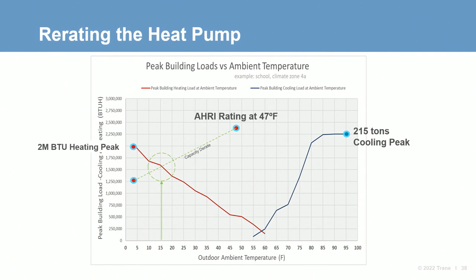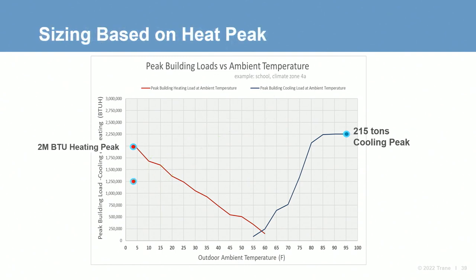To properly size heat pumps for this plant, we need to use the heating peak as our starting point. For our example, sizing based on heating peak would require around 330 tons of cooling capacity, which is over 50% more capacity than what is required on the cooling side. The next topic we need to discuss for unit sizing is defrost. Dan's going to walk us through the basics.